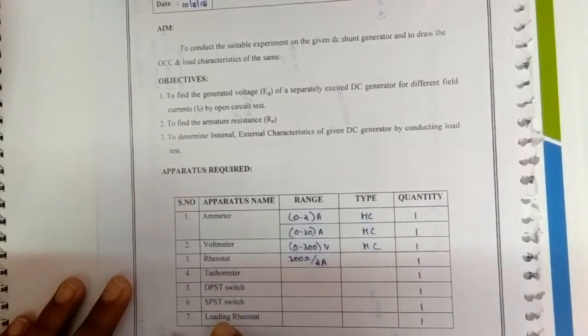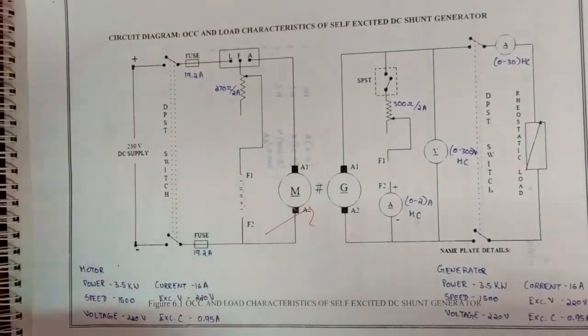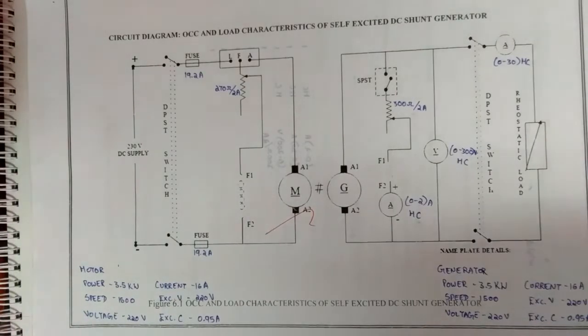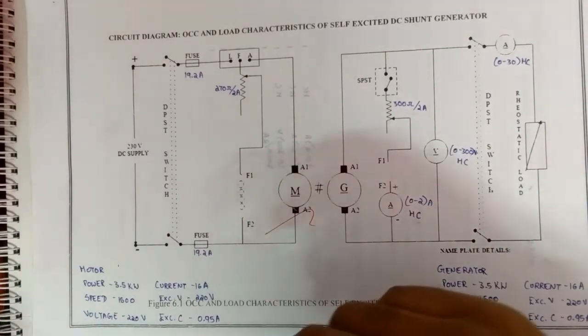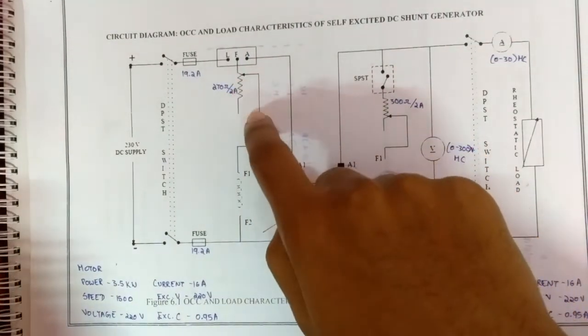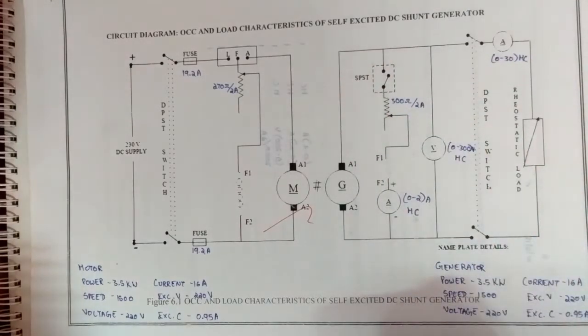Before moving to the procedure, first we should take care of the precautions. The motor field rheostat should be kept at minimum position at the time of starting. The generator field rheostat should be kept at maximum point at the time of starting. The DPST switch 2 is open during the open circuit test.